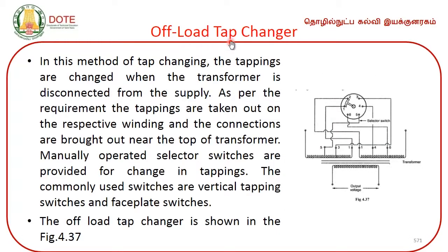Off load tap changer: in this method of tap changing, the tappings are changed when the transformer is disconnected from the supply. As per the requirement, the tappings are taken out on the respective winding and the connections are brought out near the top of the transformer. Manually operated selector switches are provided for change in tappings. The commonly used switches are vertical tapping switches and faceplate switches. The off-load tap changer is shown in figure 4.37.